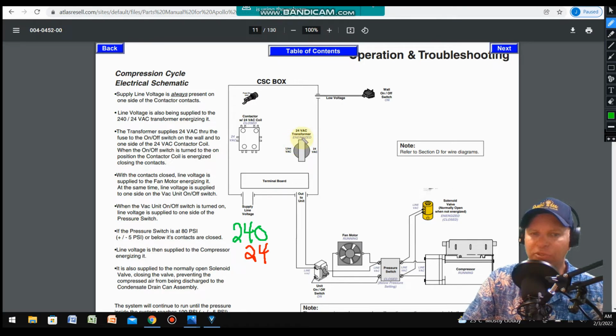The first thing we'll talk about is the supply voltage, which is 240 volts. That voltage is coming into one side of the compressor control box. Then we have what's called a contactor. A contactor is a device where you control a large voltage with a smaller voltage. In this case, we're controlling 240 volts with 24 volts. The way that we get that 24 volts is we use something called a step-down transformer. This step-down transformer converts 240 volts into 24 volts.